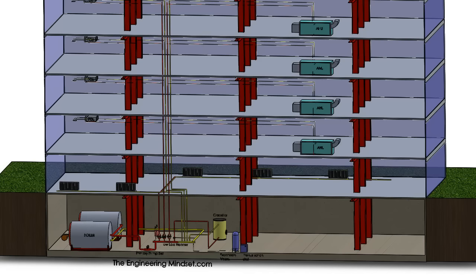Now as you can see we've got two large boilers over here, and they are piped in parallel. What that means is that both boilers can operate at the same time or individually, so one could be isolated and cut off and opened up for maintenance while the other boiler continues to run and provide heating to the building. This is the most common type of configuration for modern heating systems. The other version would be series, and for this type of building that's not really practical.